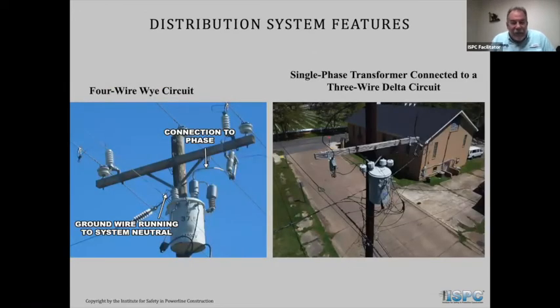All right, 4-wire Y circuit. You can see the system neutral. It's not real clear, but you can see the system neutral right behind the transformer. It's actually on the other side of the pole. And then the picture on the right is a 3-phase delta system. So there is no neutral. All of the return current coming from that building on the right that you see is going to go through that transformer to the ground and down to the earth.